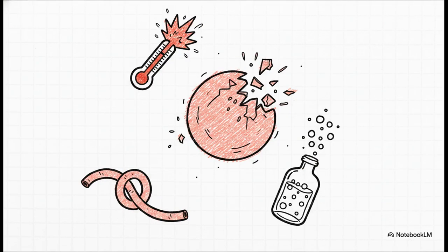Another super rare but critical mechanical glitch is hemolysis, the actual fragmentation and bursting of red blood cells. This can happen if the dialysate heater malfunctions and spikes above 47 degrees Celsius, if contaminants like bleach sneak into the water, or even just from the mechanical stress of kinked tubing. Just like a type A reaction, if hemolysis happens, stop everything and do not return that hemolyzed blood to the patient. It is packed with intracellular potassium and will cause immediate, life-threatening hyperkalemia that can literally stop the heart.